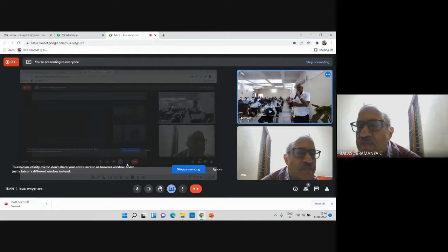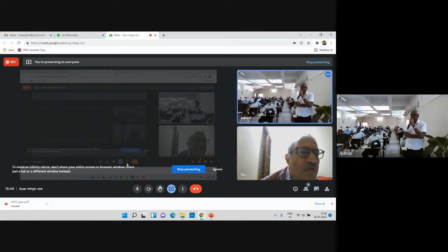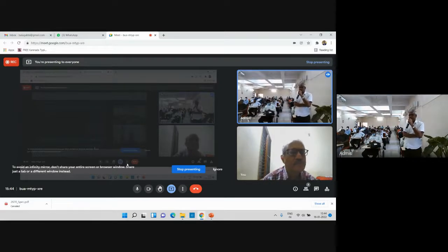Yeah, please. If there is a loss of data from the meter to the system, do you have any tips on how to tell whether it is a network error or whether the metering connection was defective? Because when the network operator is approached, he says the network is always available 24 hours, but there may be an issue with the meter device. When I open the meter device, there may be a connection module failure also.